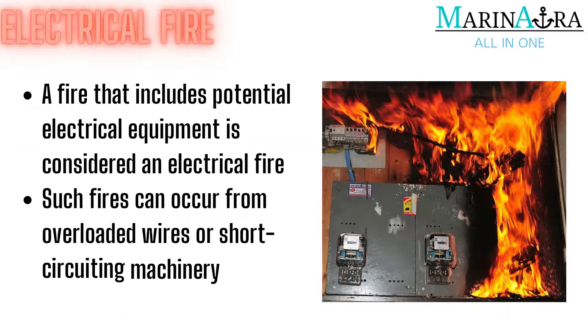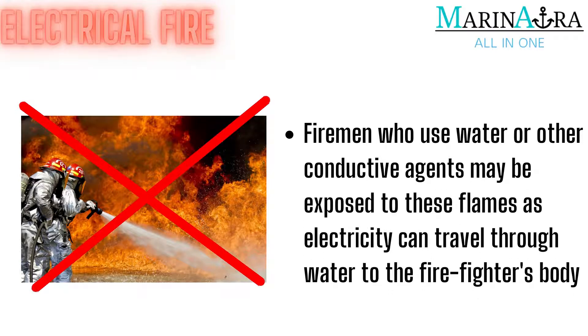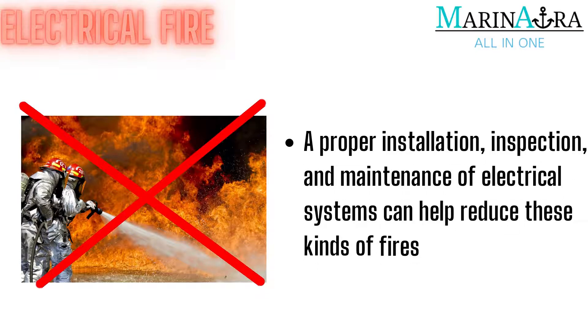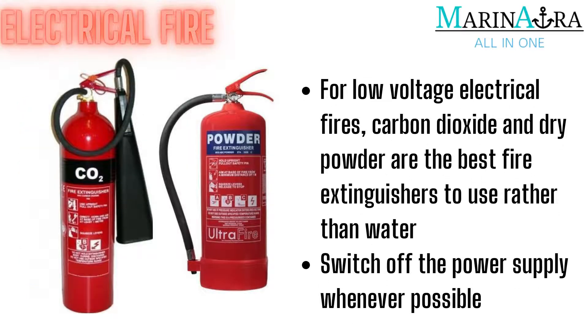Electrical Fire. Electrical fires are defined as fires that include potentially electrified electrical equipment. Short-circuiting machinery or overloaded electrical wires can create this type of fire. These flames can pose a serious risk to firefighters who use water or other conductive agents, as electricity can be carried from the fire, through water, to the firefighter's body, and ultimately to the ground. Making certain that electrical equipment and systems are properly installed, inspected, and maintained will help to decrease the danger of this sort of fire. While water should not be used to extinguish an electrical fire, other forms of fire extinguishers such as carbon dioxide and dry powder can be used in low voltage circumstances. If possible, always switch off the power supply.